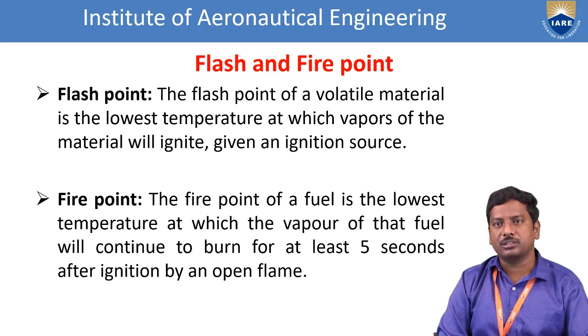So for these substances, the flash point is the lowest temperature at which the vapors of the material will ignite. Ignite means burning takes place, given an ignition source. So this is the definition of a flash point. Once again I repeat, the flash point of a volatile material is the lowest temperature at which vapors of the material will ignite given an ignition source.